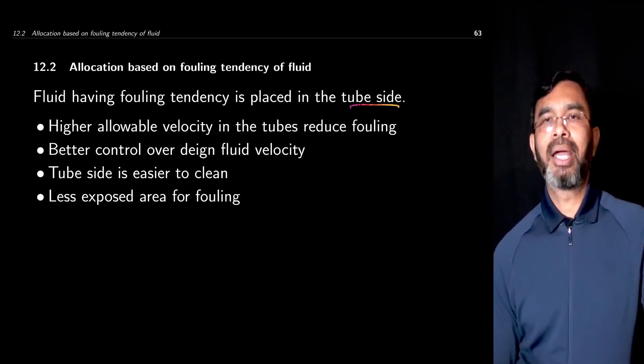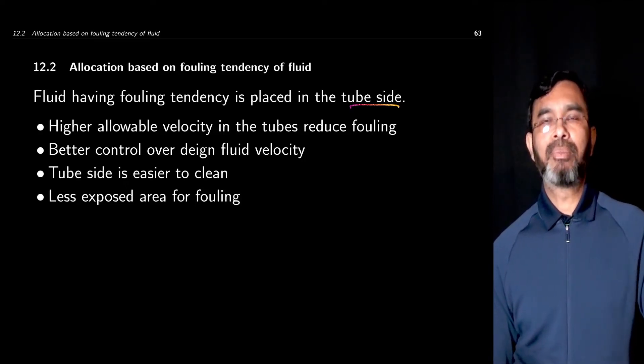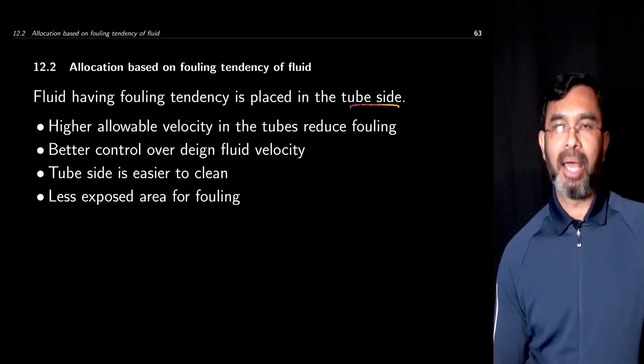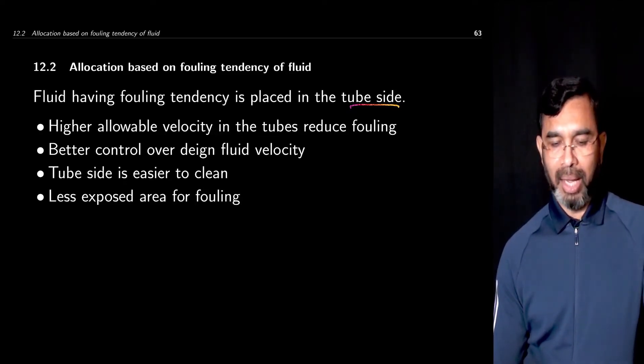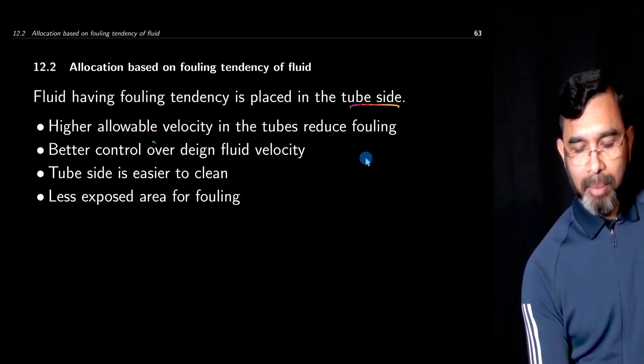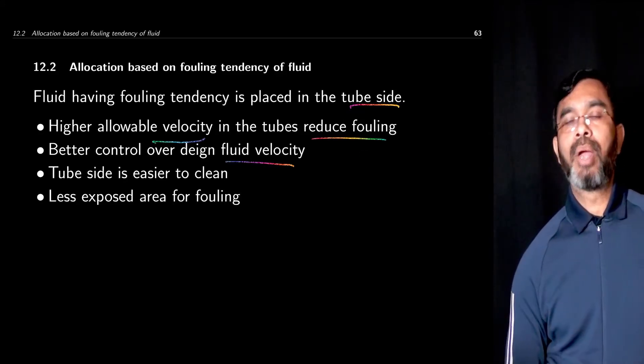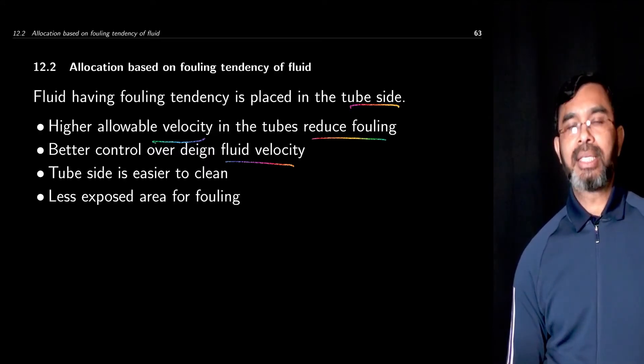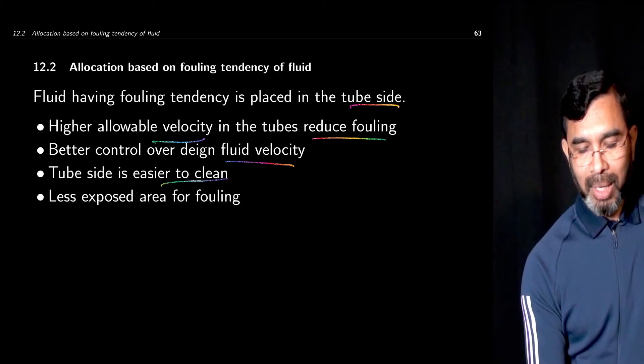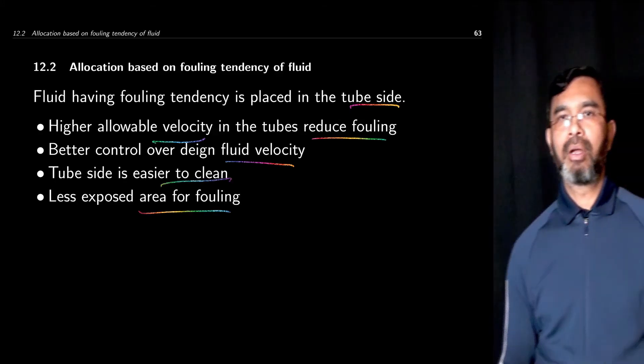If fouling fluid is placed on the shell side, fouling will take place on the outer side of the tubes as well as on the shell, baffles, and other construction items. On the tube side we can allow higher velocity and thus reduce fouling. We have better control over the design fluid velocity for the tube side, the tube side is easier to clean, and there is less exposed area for fouling.